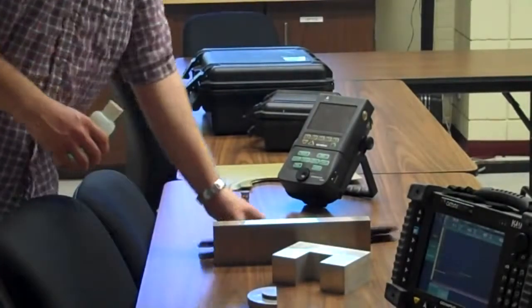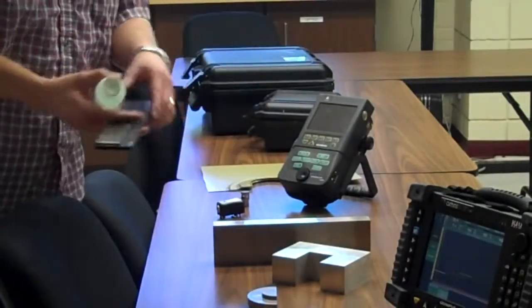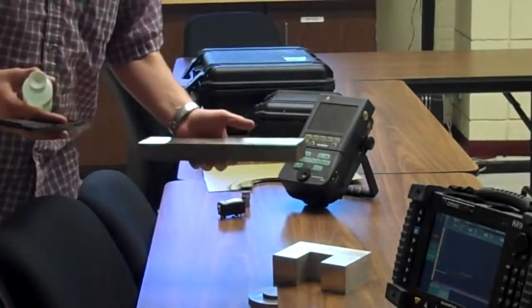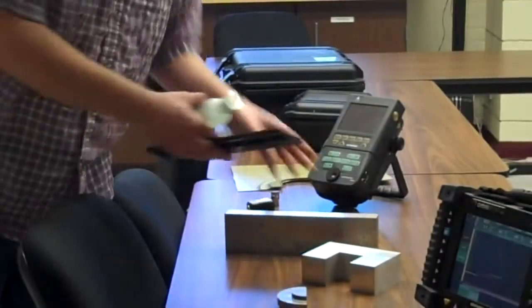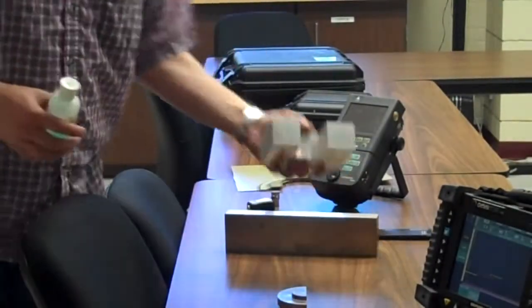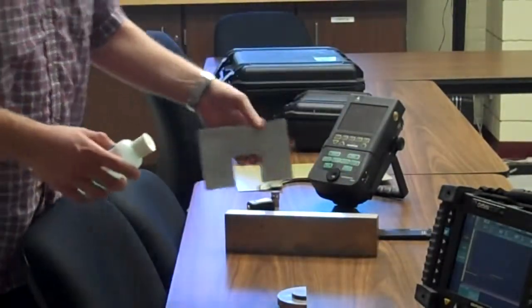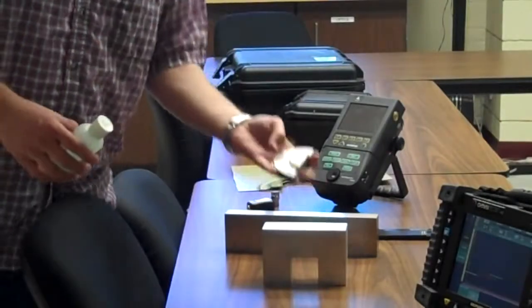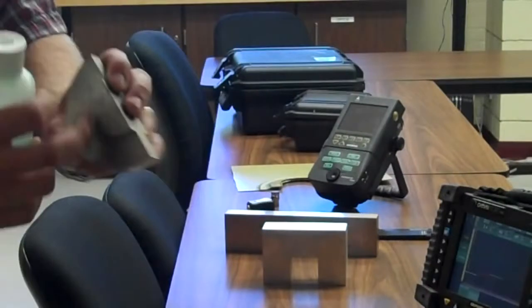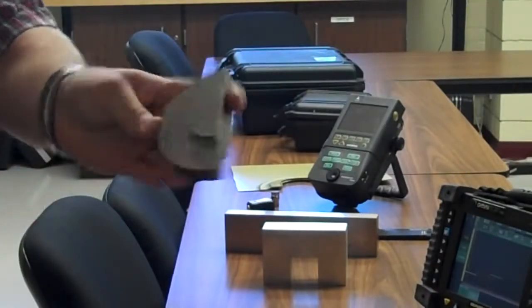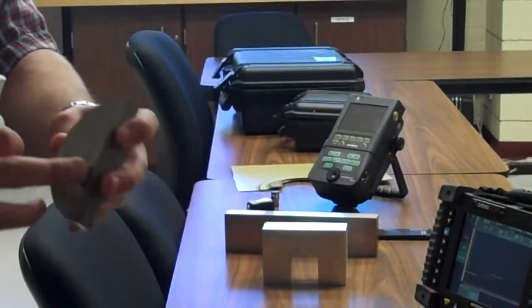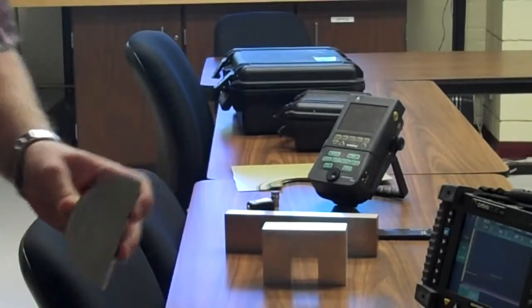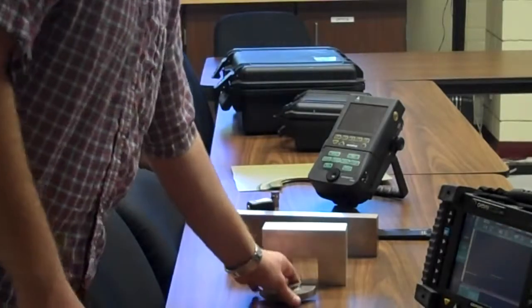And then just some stuff that we can test, a piece of composite, a little reference standard that we got. This is a NavShips block, a NavC block. This is a resolution block that we get into when we get into actual calibration. We also have another little DC block here, which is just distance. A couple radiuses here so we have some common ground on distance, 1-inch radius, 2-inch radius. Then just our standard bottle couplant.